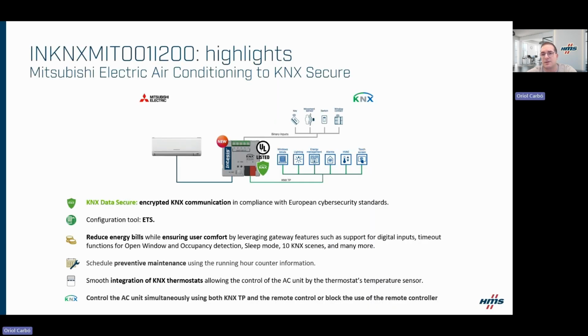Let's see now the key functionalities available in the KNX Secure AC gateways for Mitsubishi Electric. From a functional point of view, the gateway helps reduce energy consumption while maintaining user comfort by using features such as digital inputs, open window detection, occupancy control, sleep mode, and KNX scenes. The gateway supports up to 10 KNX scenes, which can be saved and triggered directly from the KNX system. It also allows preventive maintenance to be scheduled using the running hours counter, giving better visibility of system usage.